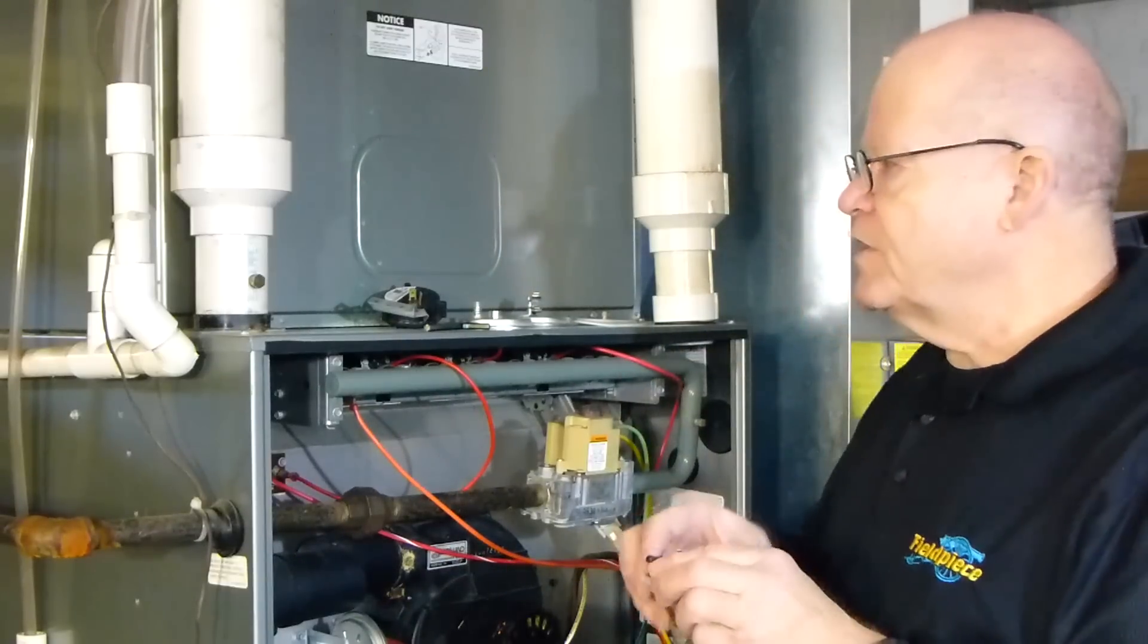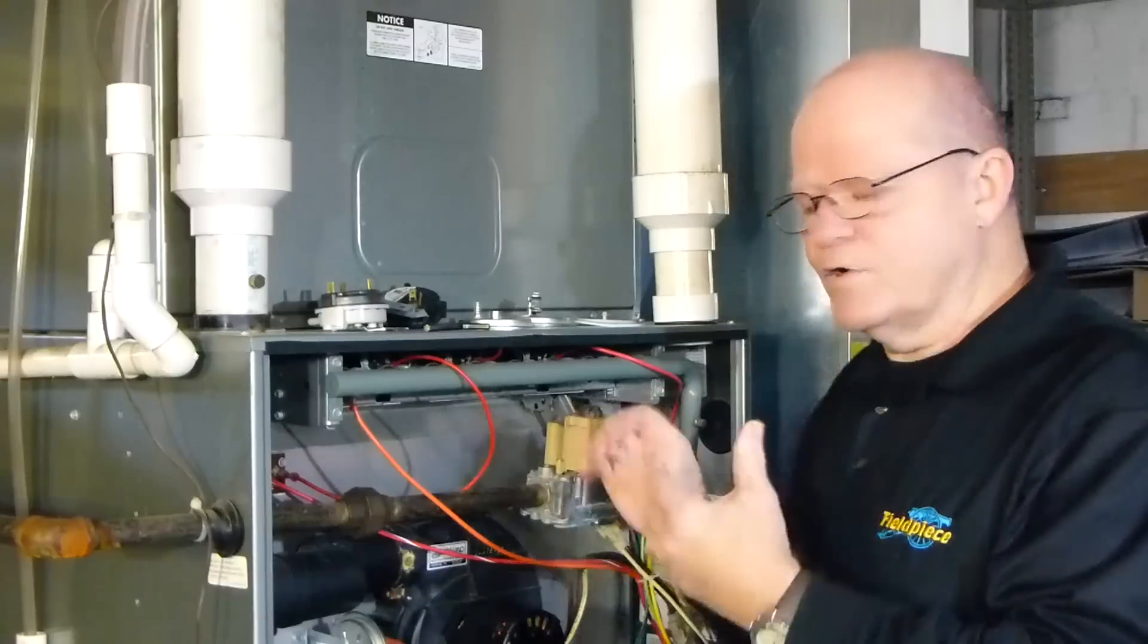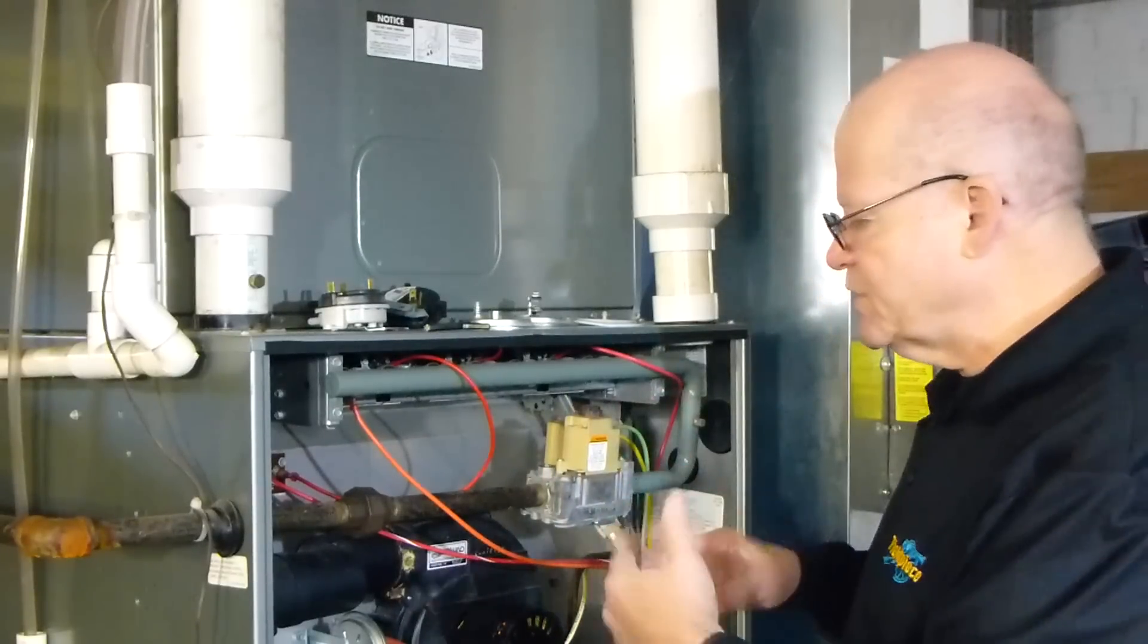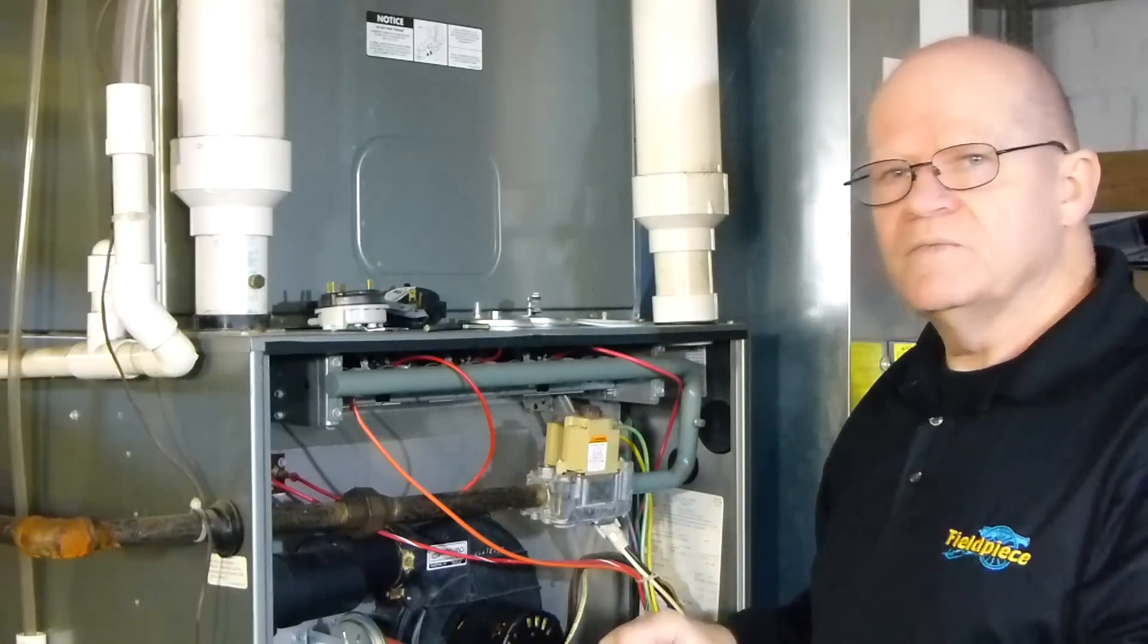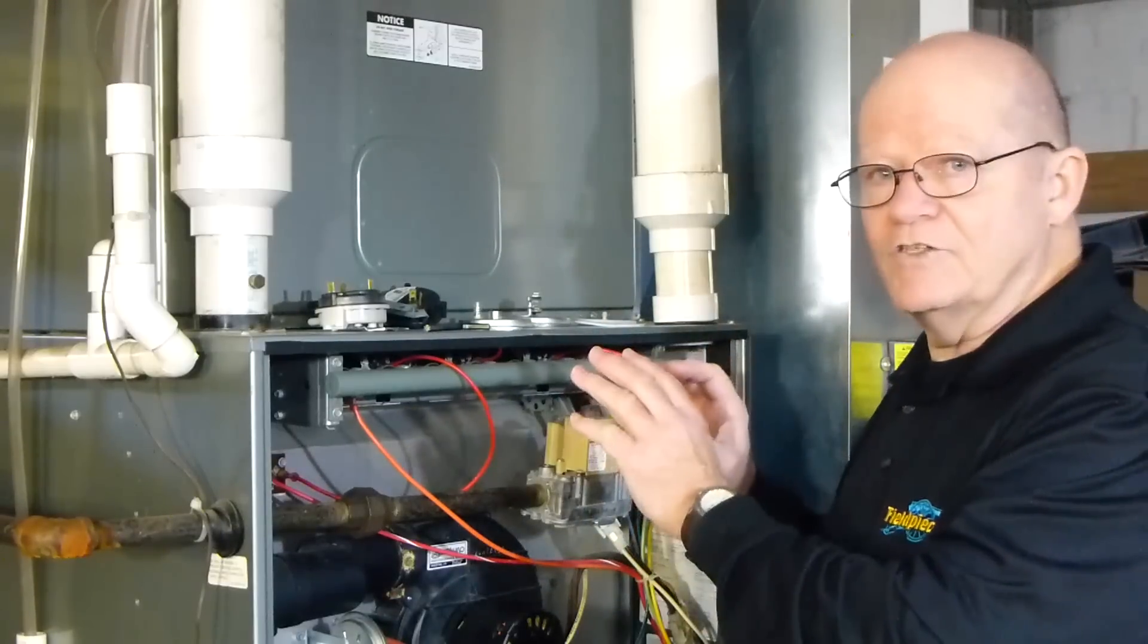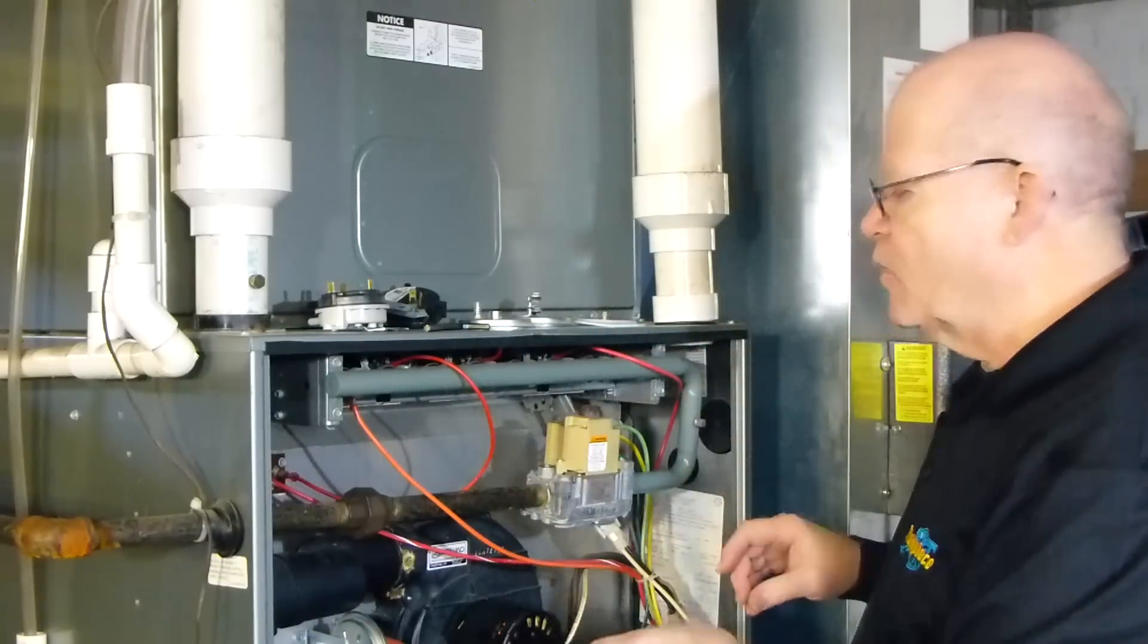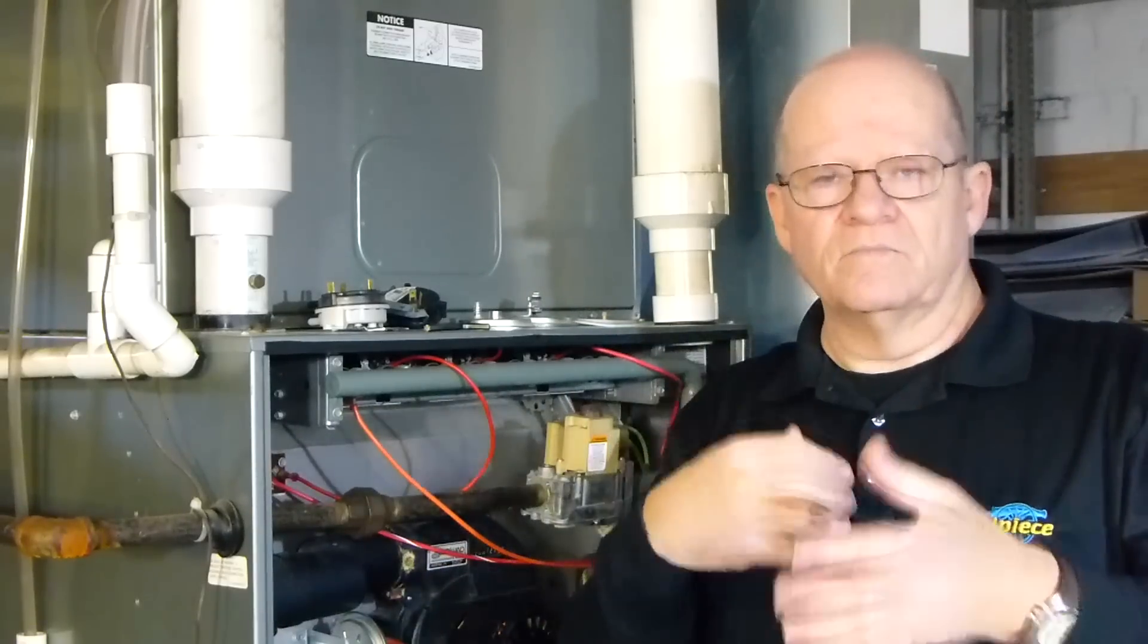So if you're testing a dual pressure switch, test the negative side. That's going to give you all the information that you need. The other thing is when it's hooked up to the furnace, what you'll see is one side hooked up to either the collector box or the inducer, and the other side is tied into the burner or the gas valve and the burner box.